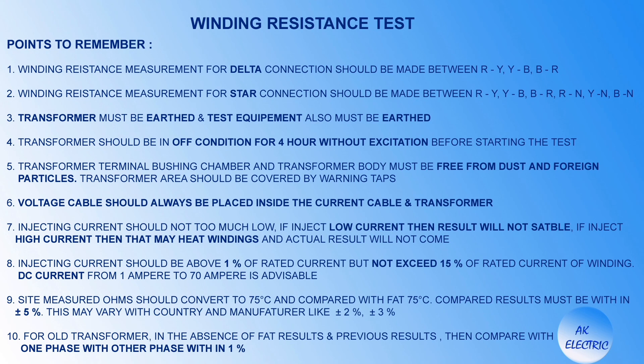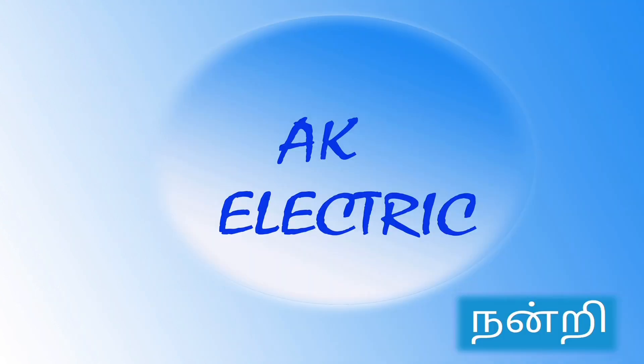DC current from 1 ampere to 70 ampere is advisable. Site measured ohms should be converted to 75°C and compared with FAT 75°C values. Compared results must be within plus or minus 5 percent — this may vary by country and manufacturer, such as plus or minus 2% or 3%. For old transformers without FAT results or previous records, compare one phase with another — that must be within 1 percent. I hope this video is informative to everyone. If you like this video, subscribe, like, and click the bell icon. Thank you.